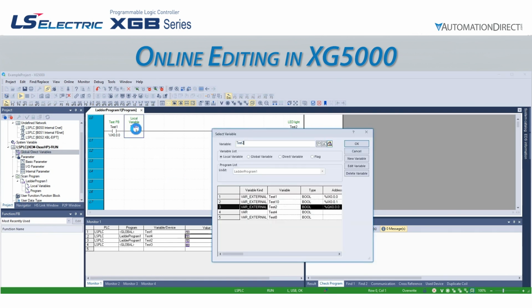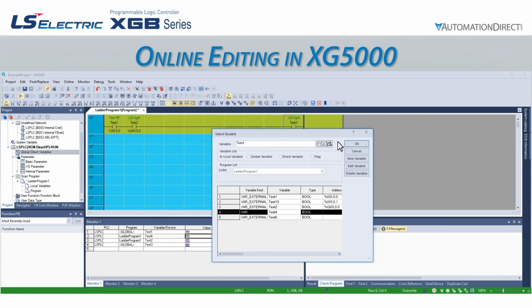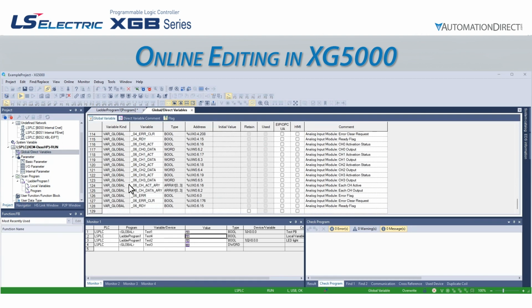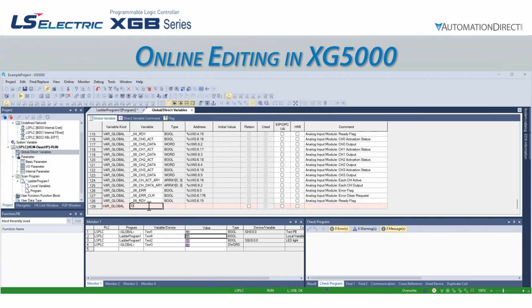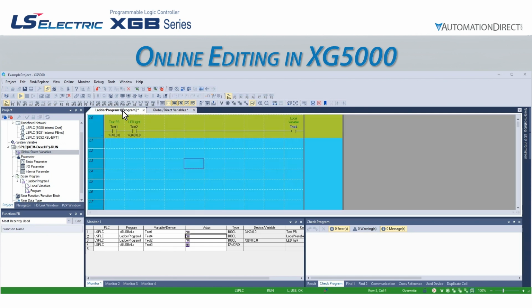Let's swap the test4 and test2 variables in the logic and create a global variable called online test. These changes are only present in the software since we haven't sent them to the CPU yet. It is important to note that during this time, the logic monitoring will not function accurately, as the changes we have made are not yet in the CPU.